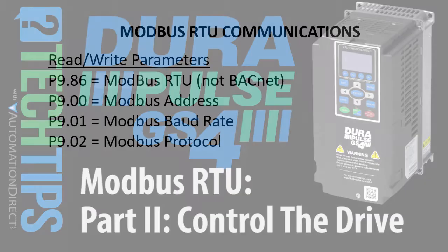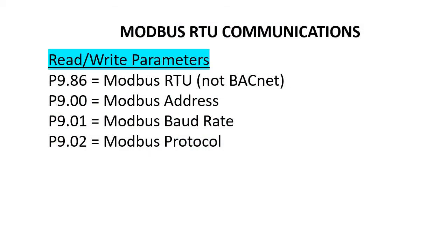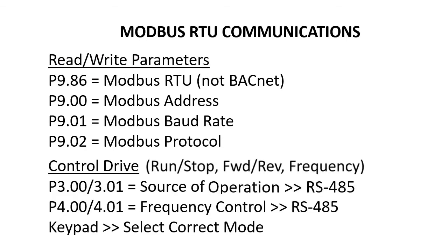In part 1, we saw how to set up a GS4 drive to read and write parameters via Modbus RTU. In this video, we'll learn how to command the drive to run, stop, and change frequency using the same Modbus Poll application we used in part 1.